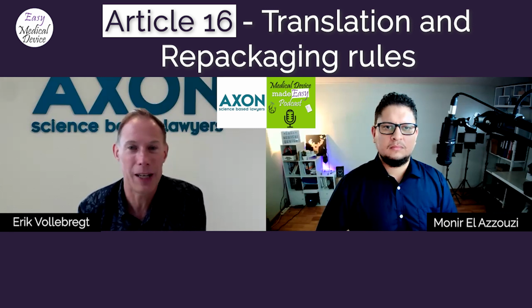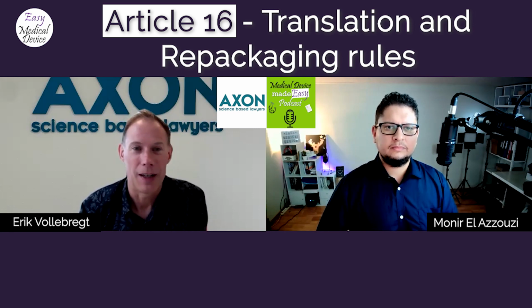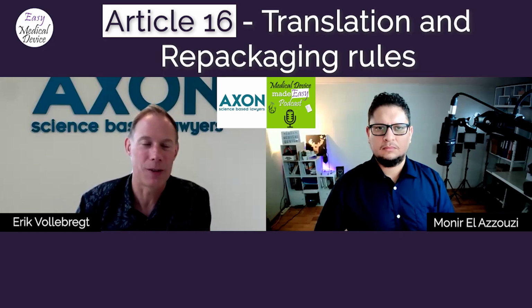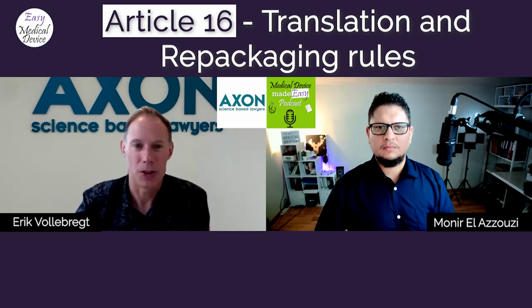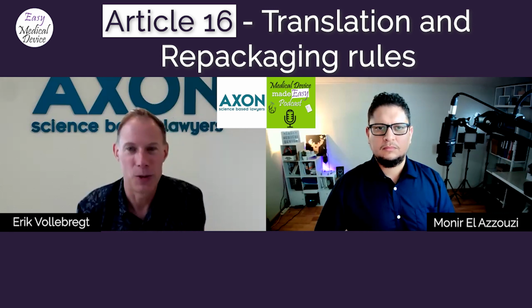Until in 2020, I think in August, I don't know exactly the number of that MDCG document again, there was a Q&A about Annex 7. Okay. And in that Q&A, it said, hey, by the way, about Article 16 certification, that is not conformity assessment. So that means that we, as the MDCG, have nothing to do with it within the scope of conformity assessment, and notified bodies can stop being uncertain about what the nature of that certification activity is. They can just go ahead and do their own certification on the standards of that provision.